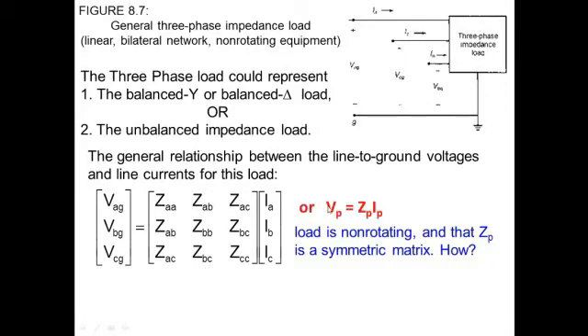We can simply write that the phase voltage equals the phase impedances multiplied by the current matrix. Or, if we write the same matrix in the form of sequence voltages, sequence currents, and sequence impedances, we can write that the sequence voltage equals the sequence impedance times the sequence current. The sequence impedance matrix includes the zero sequence, the positive sequence, the negative sequence, and the mutual sequence between zero and positive, and zero and negative.